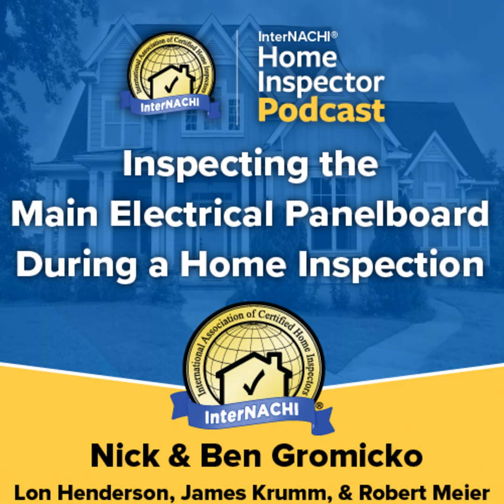The home inspector should know that the International Residential Code, or IRC, and the National Electric Code, or NEC, provide exceptions to the general rule for overcurrent protection ratings of breakers and the connected wire sizes that are for only air conditioning and heat pump equipment. Branch circuits for the air conditioning equipment and big motors may have an overcurrent protection device rating that exceeds the conductor ampacity, and this is not a defect or an electrical violation.